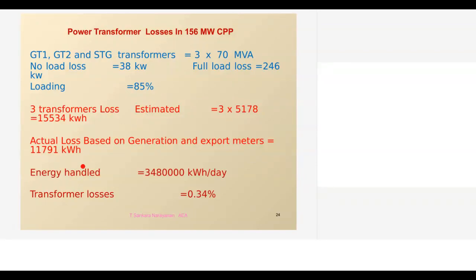And the power plant was handling so many units per day. Now, for the units handled, the transformer loss is only 0.34%. That means this is inclusive of both no load loss and load loss. So per se, transformer opportunities are very minimal, but for loss accounting, the auditor has to account for the loss.